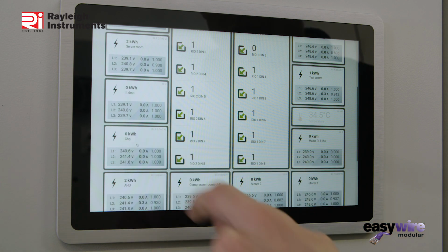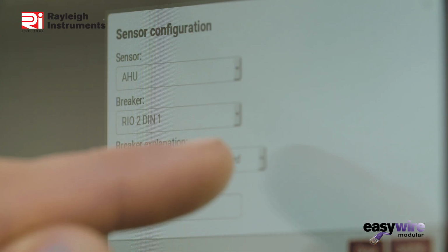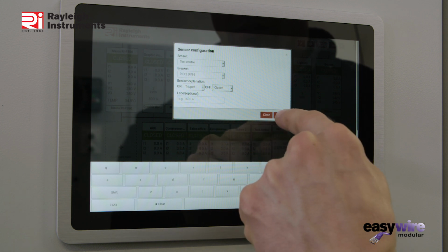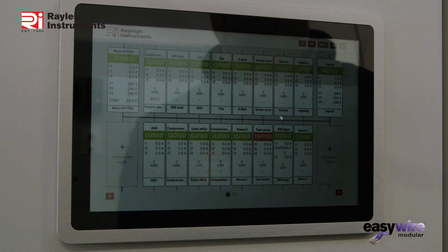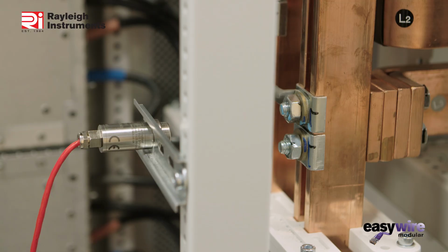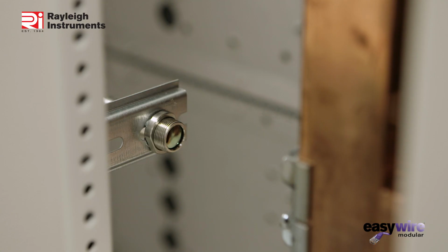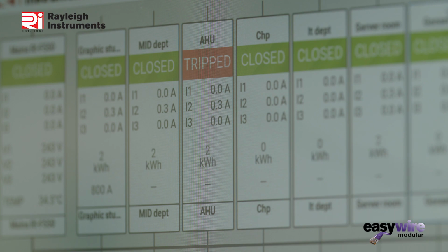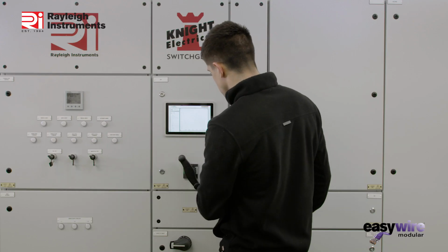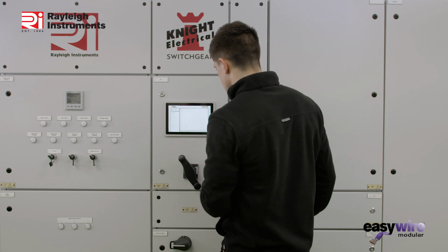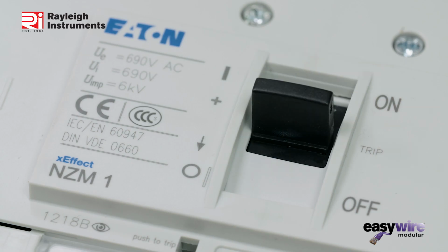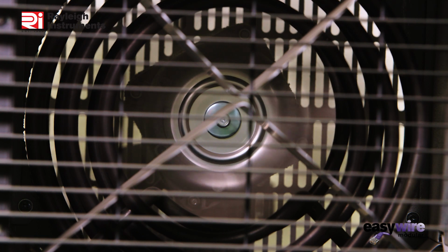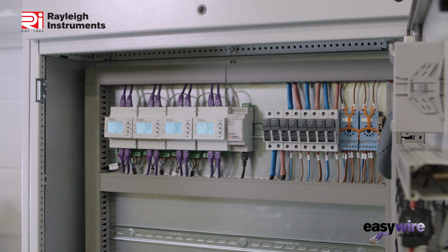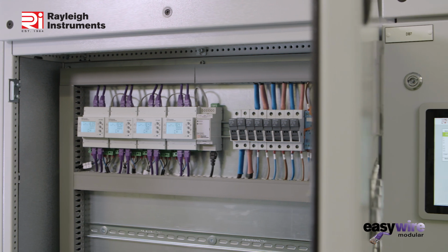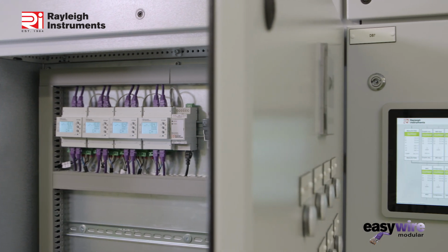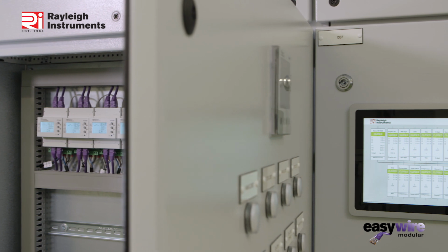The basic setup here is for monitoring meters, but easywire Modular can do so much more. You can program the MDU for preventative maintenance, monitoring bus bar temperatures, compartment temperature, breaker trip status, water ingress or fire detection. You can also program certain actions such as tripping breakers, activating fans or starting gensets. It can even interface with most smart breakers currently on the market. In fact, almost anything across all manner of electrical systems.